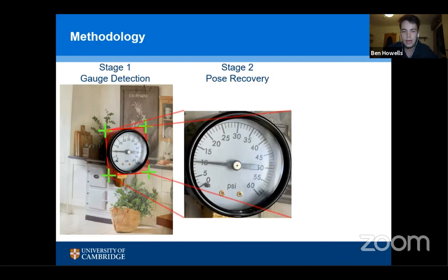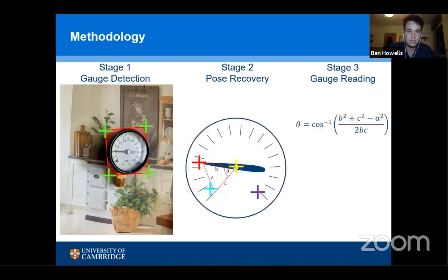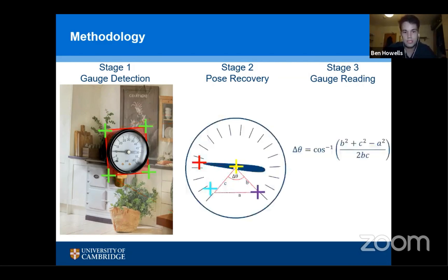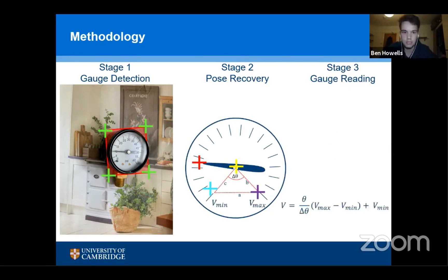We can then detect four further key points corresponding to the scale minimum, the scale maximum, the pointer center, and the pointer tip, and use basic geometry to find the position of the pointer tip and the scale maximum. We then use a linear interpolation to find the true gauge reading, provided we know the scale minimum and maximum values through OCR detection or manual entering.